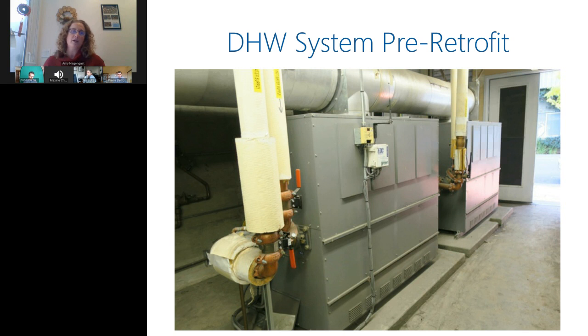You're seeing 2 domestic hot water boilers in front of you, a 1200 MBH, sitting on 2 concrete pads. I want to orient you on the concrete pads because that will be a similar scheme as we go through a couple other photos. One thing to note: it's great we were on the ground floor, since getting equipment out and in was relatively easy, though there was a ton of phasing involved, which I'll talk about in a minute. Also, up at the top, the domestic hot water boilers were all manifolded together, so all the exhaust from the heating hot water system and domestic hot water system came together and went up one flue.